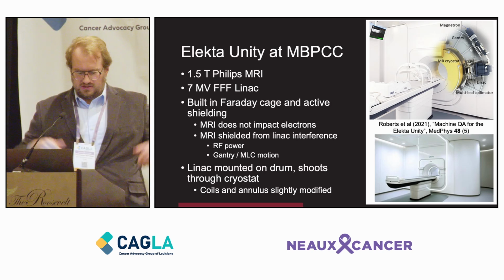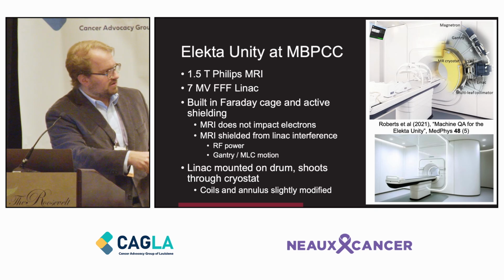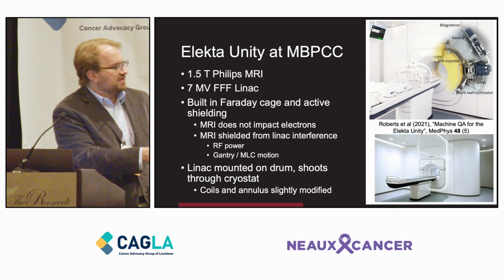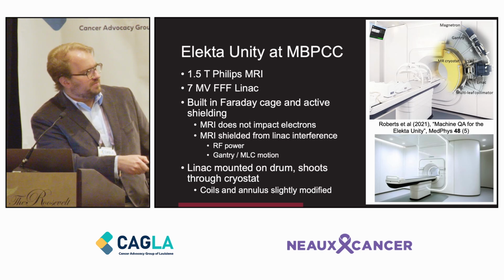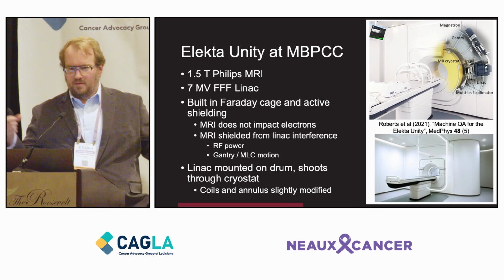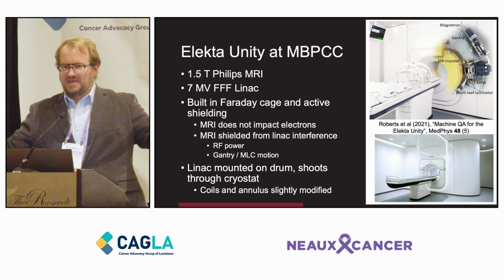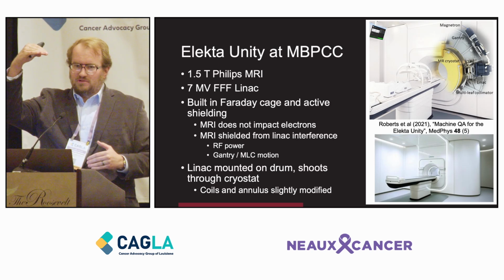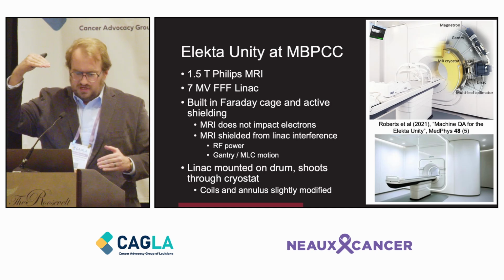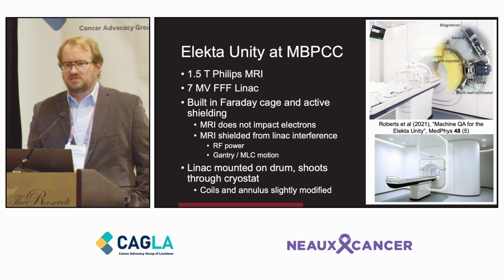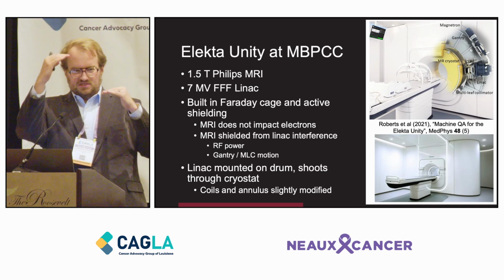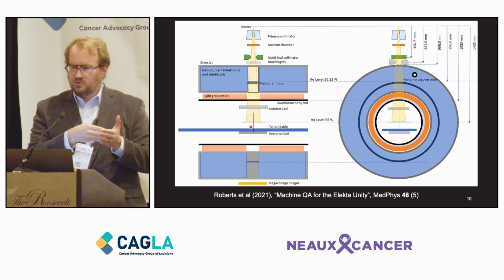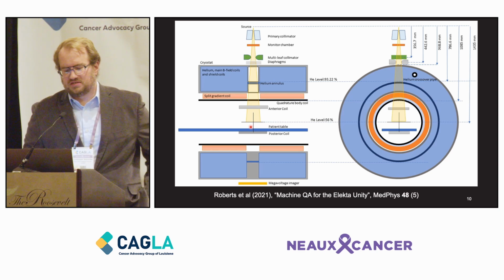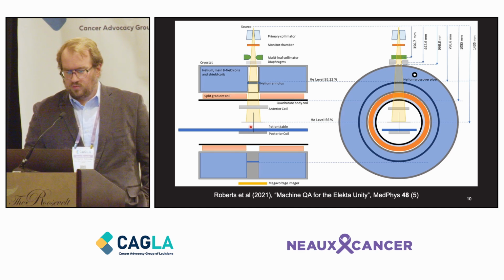Around the cryostat, if this is the annulus of the MRI where the helium is there for cooling to keep the system superconducting, there's a large rotating drum built around the outside of the cryostat that houses the linear accelerator. And we deliver the radiation beam right through the cryostat. The cryostat's slightly modified, so the helium annulus is made a little bit narrow in the center so that we're not shooting through as much material to get to the patient. But it's a pretty impressive design.